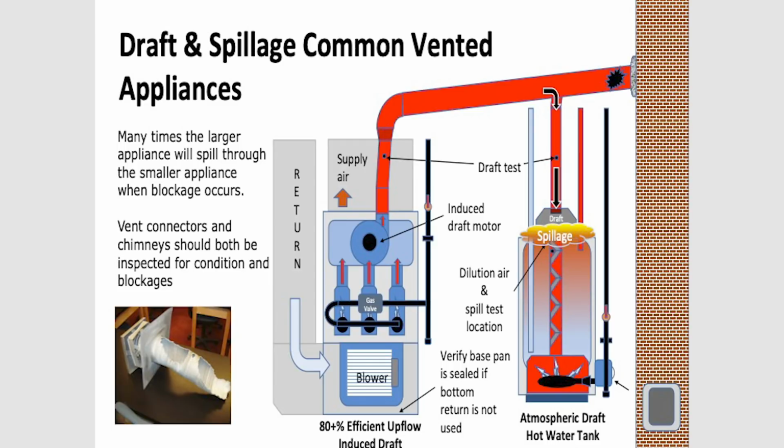So I'd start the furnace up with the kids. I'd have the draft going on there just like normal. And then I'd just decrease the draft. Walk over there, say test draft. And I'd have them check the furnace, and they go through and test everything, and they say, yep, it's all working good. And then I'd say, are you done? They say, yeah. And I said, good, you just killed your customer. And they look at me like, what? What the heck are you talking about? I'm like, come over here.